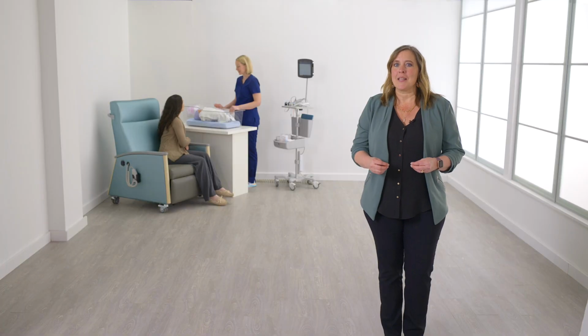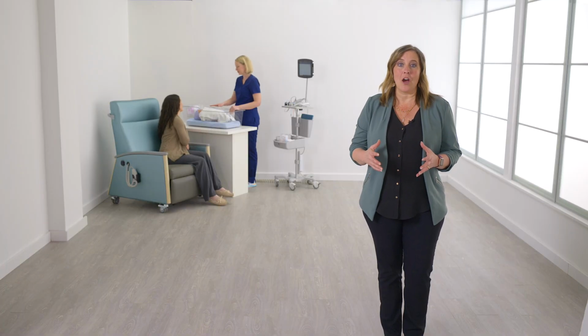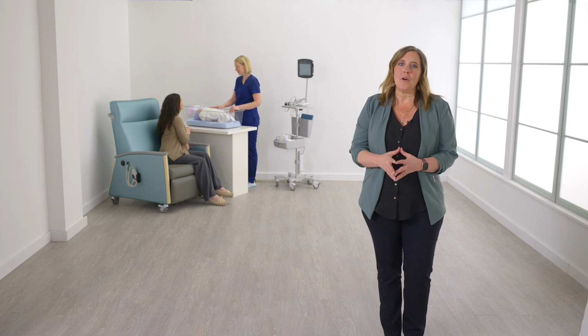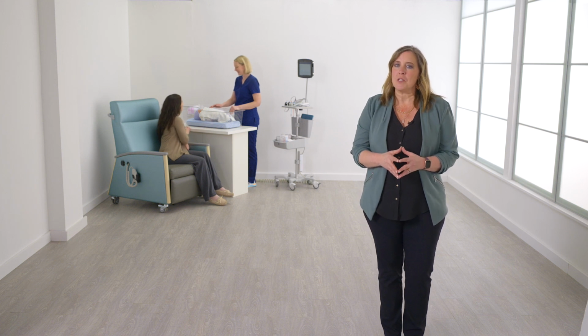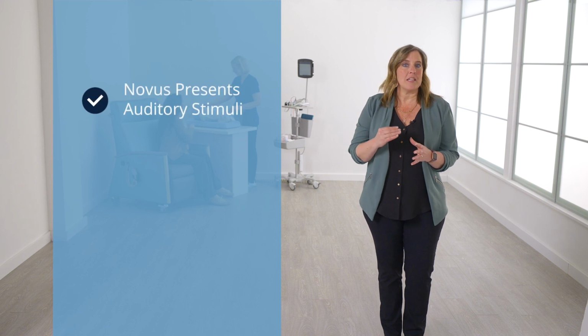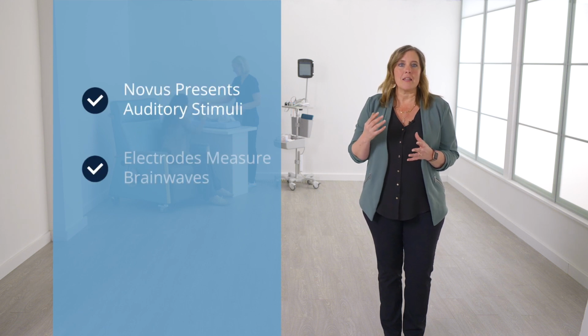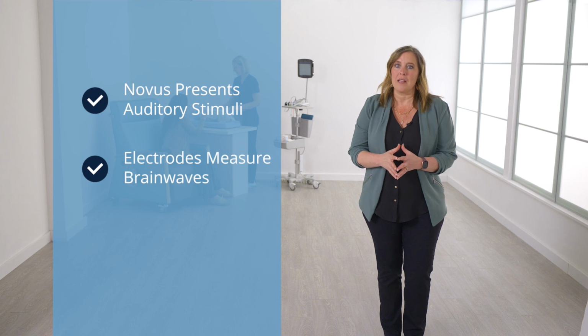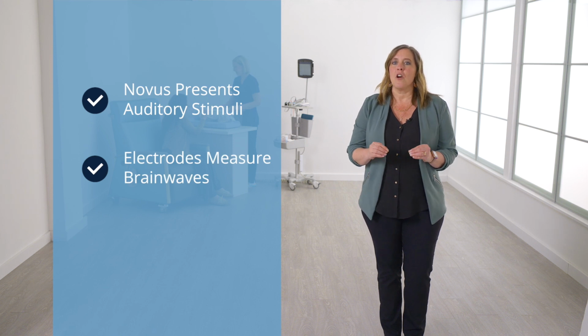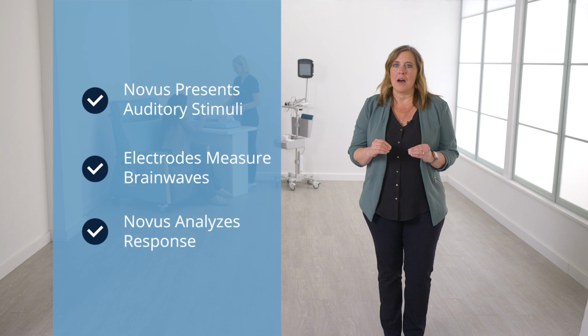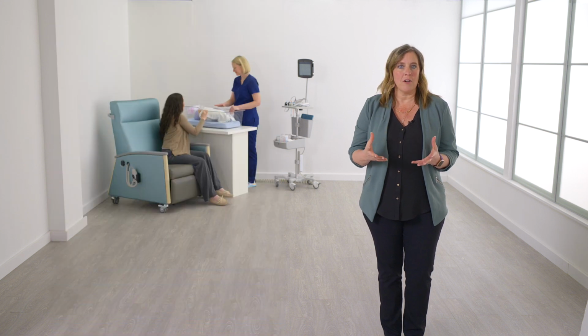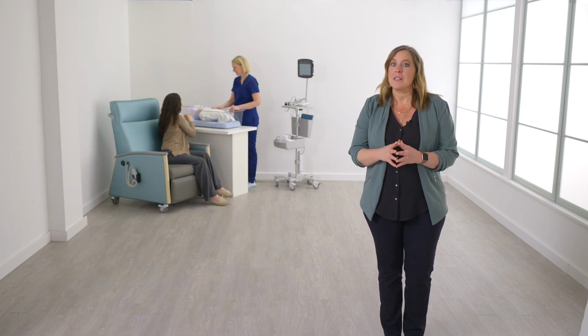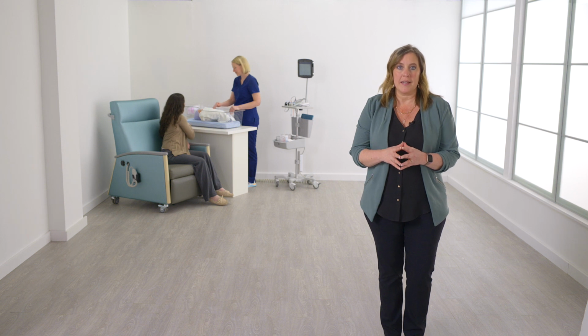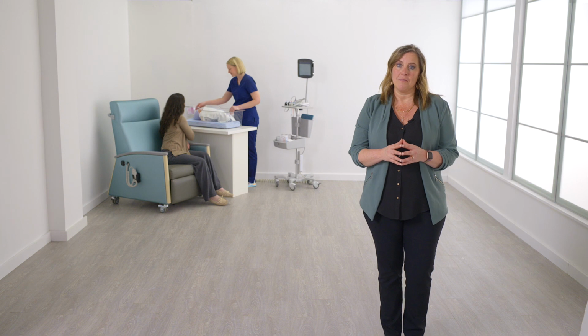Automated Auditory Brainstem Response Testing, or AABR testing, is a method of newborn hearing screening that measures the brain's response to sound. The Novus sends soft clicking sounds into the ear, and electrodes placed on the baby's head measure the brain waves in response to the sound. The Novus automatically analyzes the response and assigns a pass or a refer result. A pass means that a response to the sound was detected, and a refer means that a response to the sound was not detected.